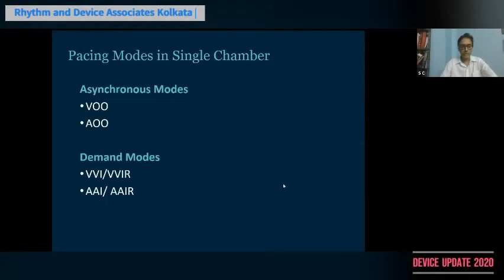What exactly is the difference in terminology? What is the difference between asynchronous and demand pacing? Asynchronous pacing paces all the time at the rate that you have set up. Demand pacing, on the other hand, is a combination of pacing with sensing. It tries to sense whether there are intrinsic cardiac events going on in the respective chambers. If there are sensed events, then your pacing intervals are changed. If there are no sensed events, the pacing pulses are delivered according to the intervals that we have set for them.